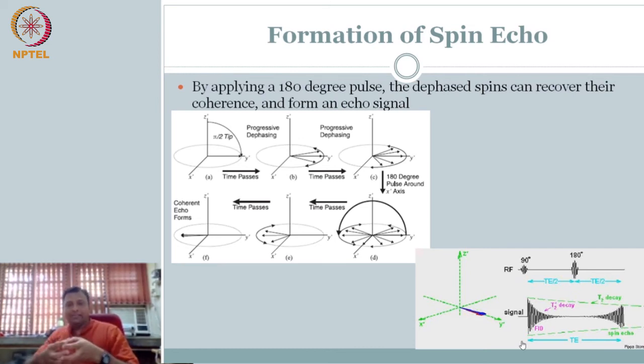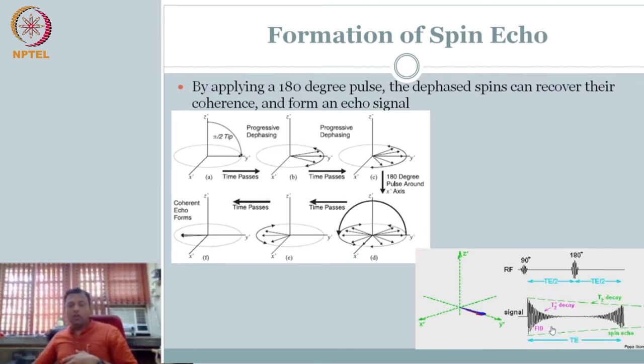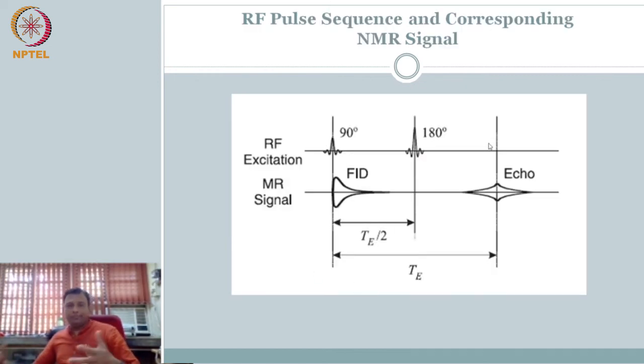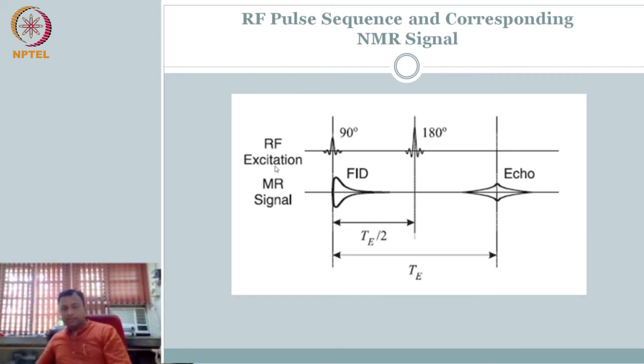This is what is called a pulse sequence — the pulse sequence can be manipulated to get whatever characteristics of the material property you want. In this limited discussion we have three characteristics: proton density, T1, and T2 of the material, which we can exploit, understand, characterize, and measure using your sequence of application of the excitation pulse, the timing involved, when you are recording, and after how long you are applying — all these are parameters of acquisition. We need some way to put all these together, which is called a timing diagram or a pulse sequence diagram.